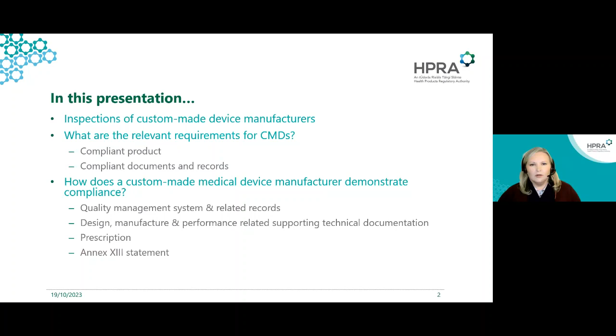So, do the HPRA or other EU competent authorities conduct inspections of custom-made medical device manufacturers? The short answer is yes. Since medical device inspections commenced at the HPRA, custom-made devices have always been considered for inclusion in each annual market surveillance plan. Article 93 of the MDR reinforces this, as there is an obligation for competent authorities to carry out market surveillance and to have an annual plan in place.